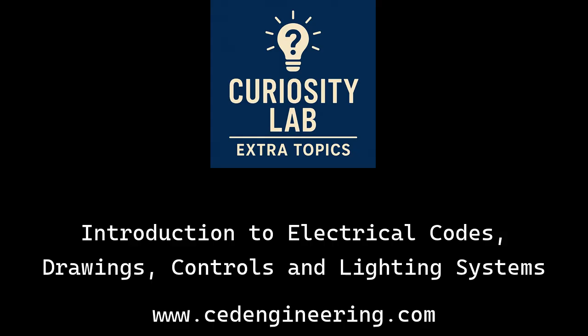How about continuous load? It's defined as a load running at max current for 3 hours or more, not counting startup. That 3-hour mark isn't random. It's why we use the 125% rule for sizing breakers and wires to handle that sustained heat buildup safely. And overcurrent versus overload. An overcurrent is any current above the rating. An overload is one type, like a motor working too hard, which causes gradual overheating if it keeps going. But overcurrent also includes short circuits and ground faults. Those are sudden, huge surges of current. Very different.